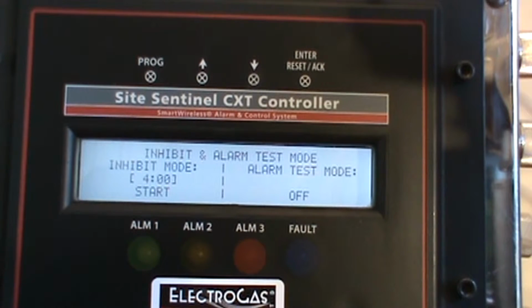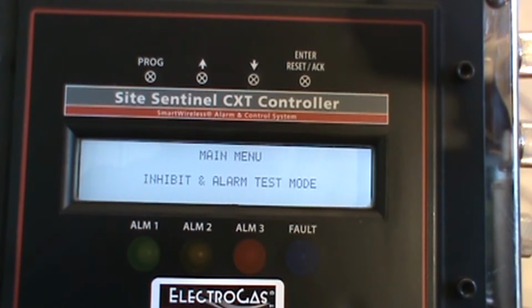I've chosen 4 as that will allow me enough time to actually bump test 2 sensors attached to this controller at once and allow them time enough to dissipate the gas so as not to go into an alarm. So I'm set for 4 minutes. I scroll with the down arrow till I've got the arrow next to start, and I press enter. And now what I've done is started a countdown, and for the next 4 minutes, no alarms will go off on my controller. After 4 minutes, it goes back into normal operating mode, and any gas exposures will trip an alarm. So you have 4 minutes now to bump test either sensor by simply exposing them to gas.